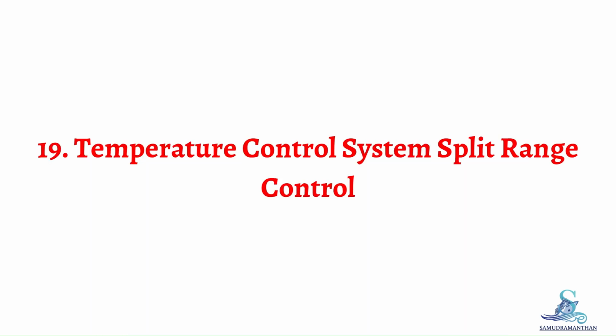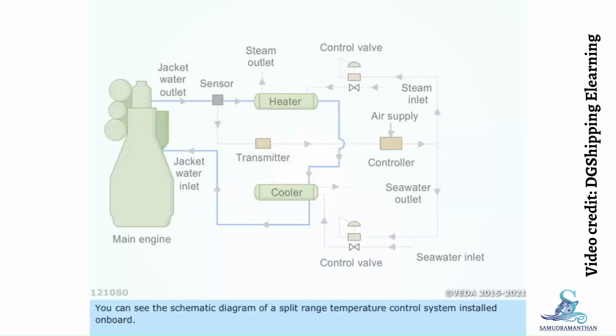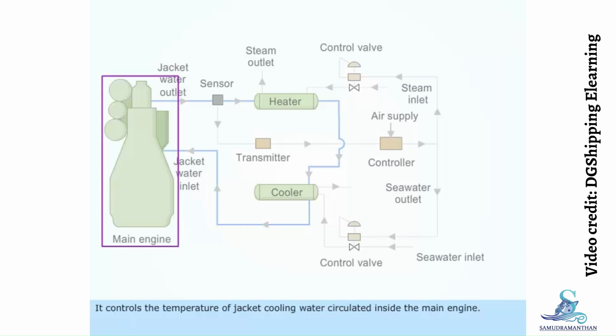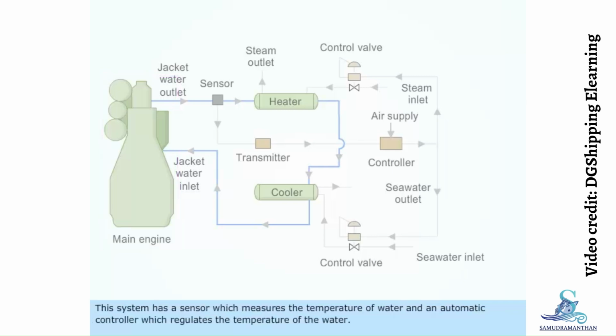Topic 19: Temperature Control System Split Range Control. You can see the schematic diagram of a split range temperature control system installed on board. It controls the temperature of jacket cooling water circulated inside the main engine. This system has a sensor which measures the temperature of water and an automatic controller which regulates the temperature of the water.